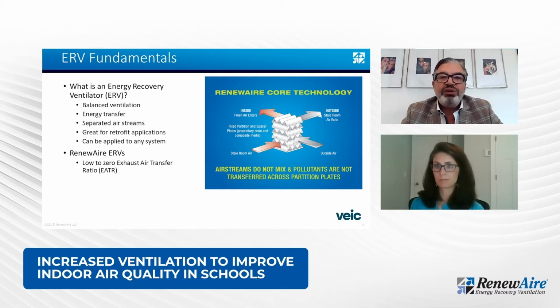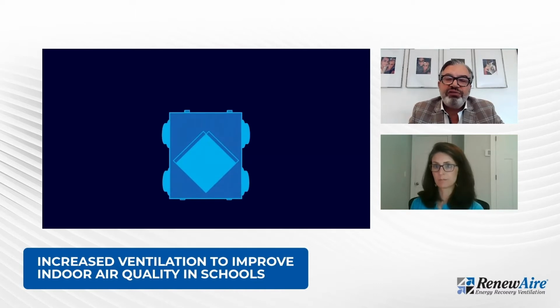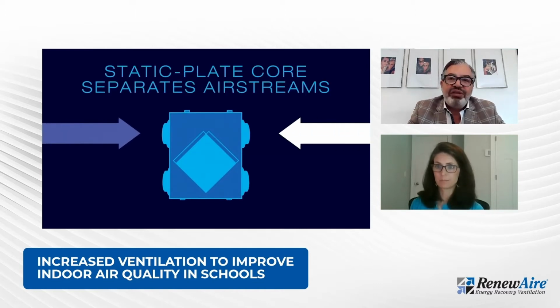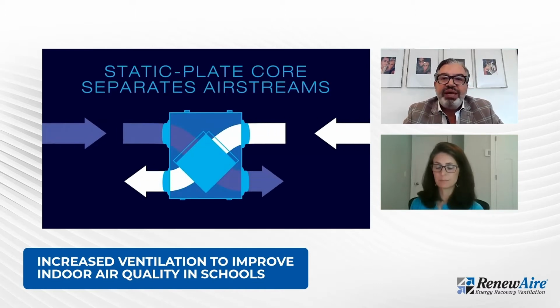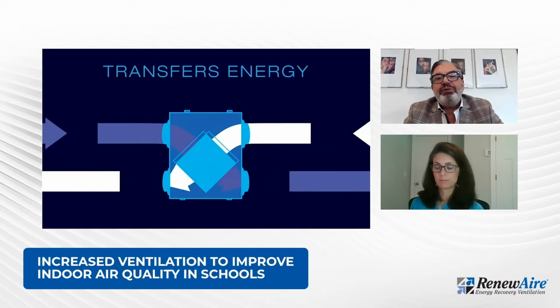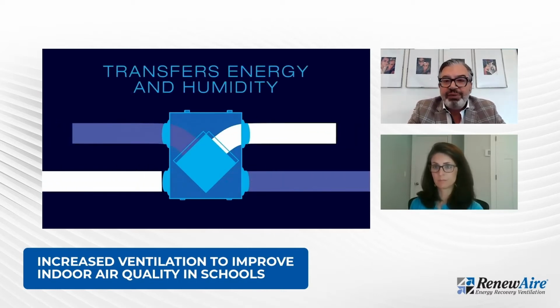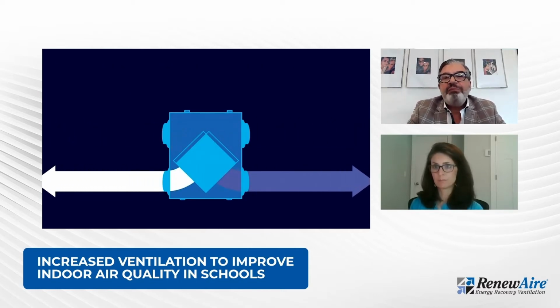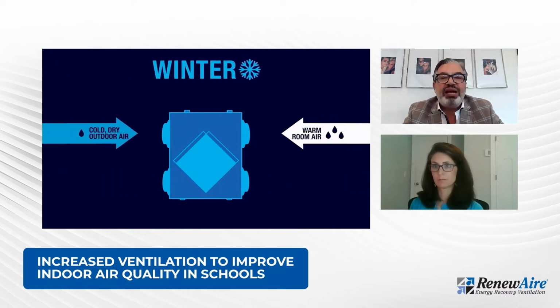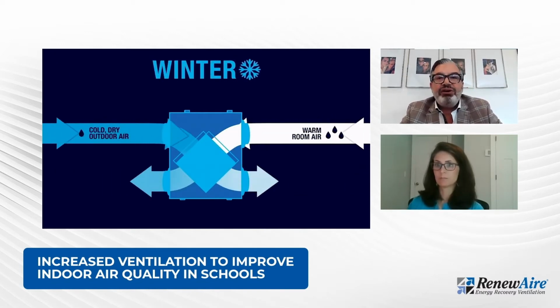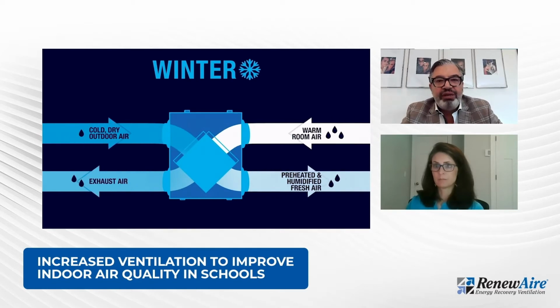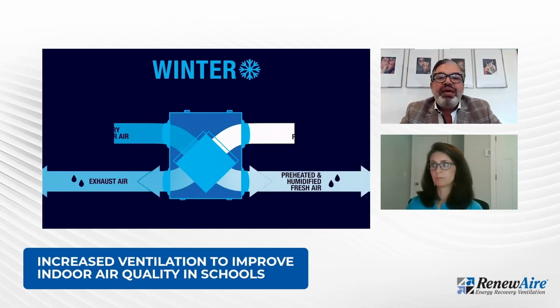Now, obviously, in the wintertime, we want to transfer the moisture from the exhaust air back to the outdoor air that's coming in. And then in the summertime, we want to take the moisture that's coming in from the outdoor air and dump it into the exhaust air and throw that out. So that tempering occurs regardless of what season you may be in.